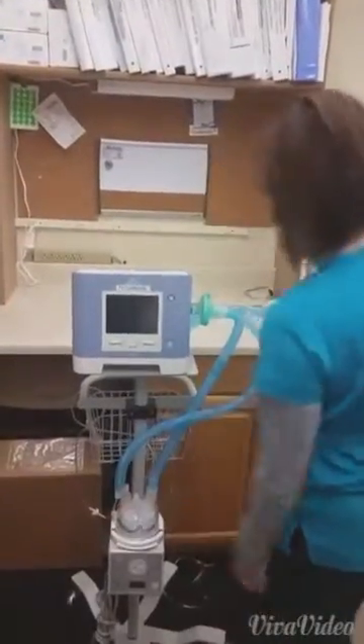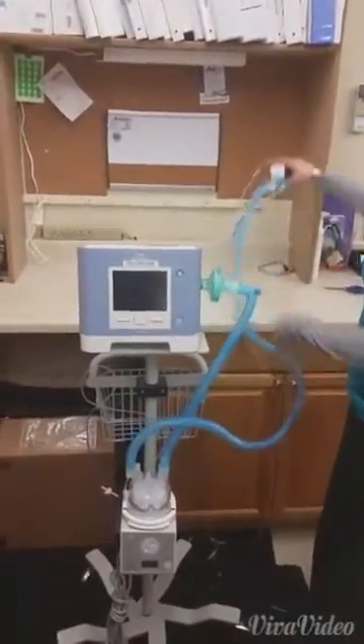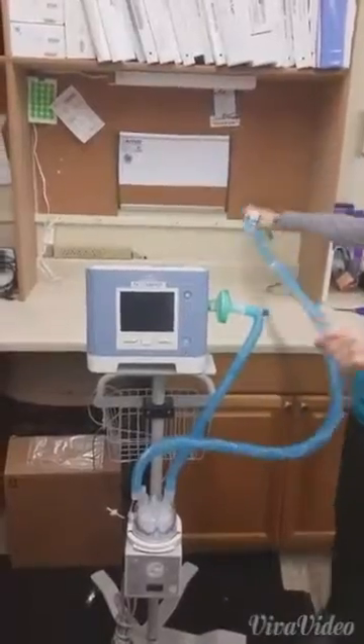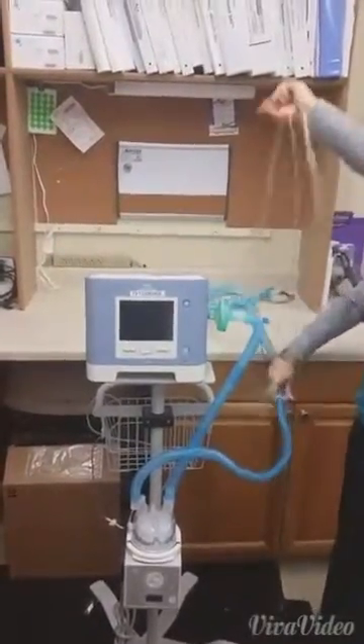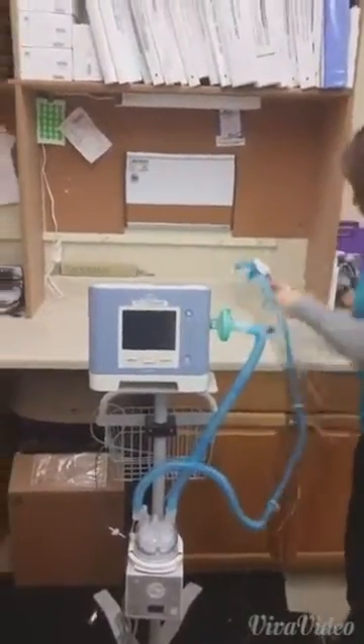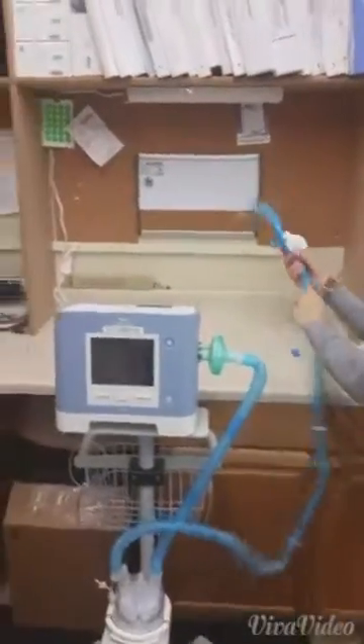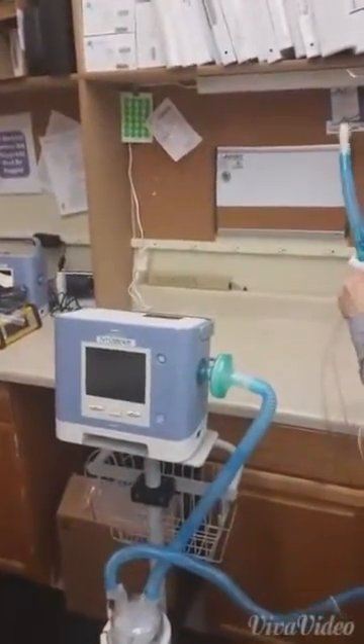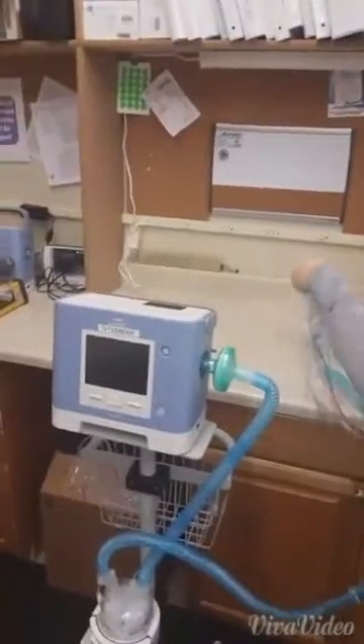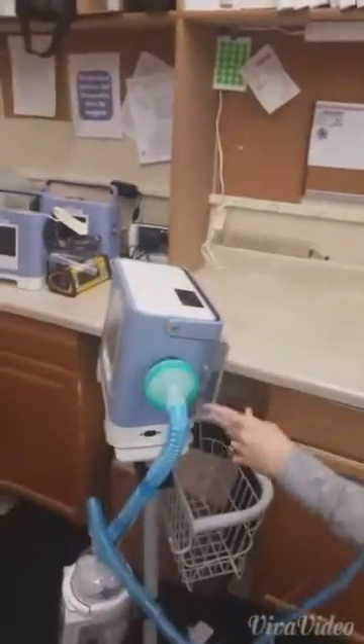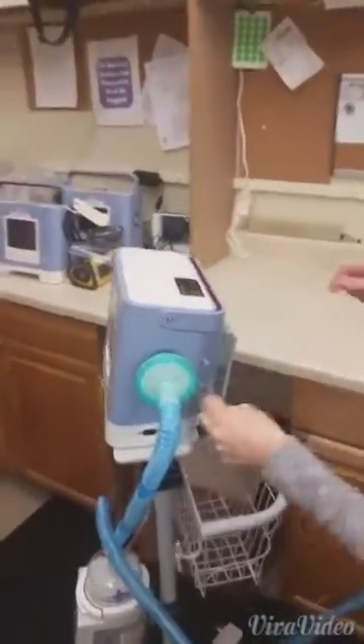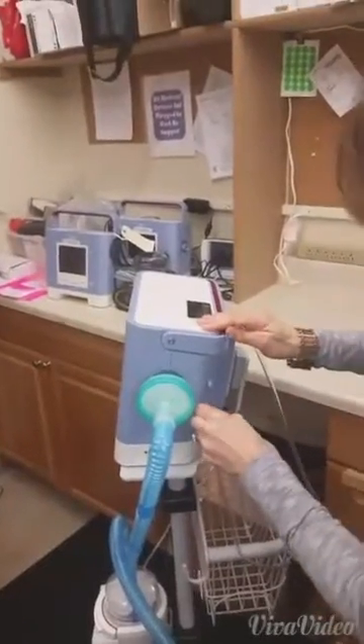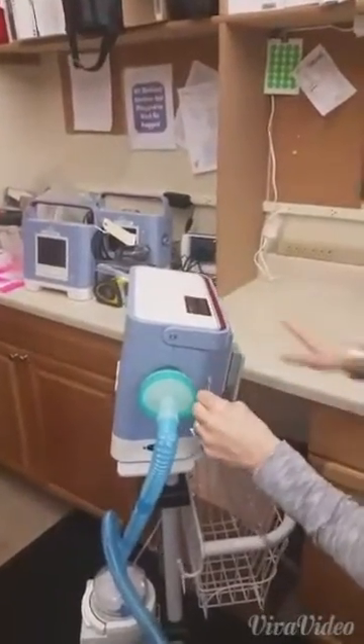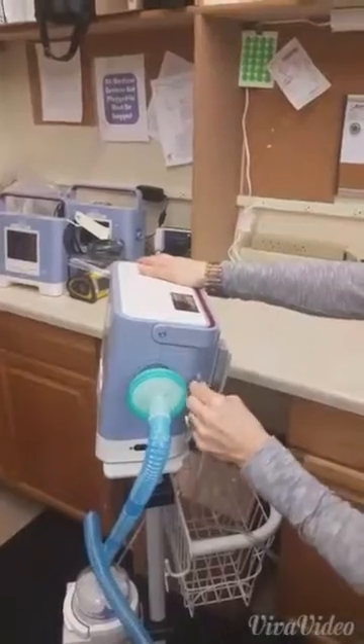Like on the other side of the heater canister. And you're going to take your tubes, and the skinnier tube is to the exhalation valve. And that's going to go plugged in on the side at the bottom to your exhalation port. And then the larger, thicker tube is going to go on the top.